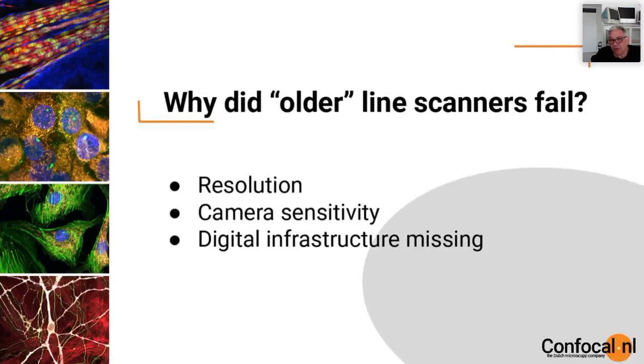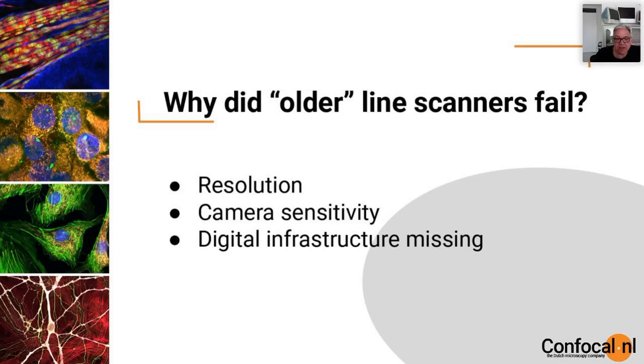Although the system design was good, commercially it failed. All the slit scanners I showed you failed because the resolution was not good enough. The cameras being used at that time — there were no scientific CMOS cameras, no EMCCD cameras, just very simple CCD chips that lacked sensitivity. Also, you could record images perhaps on videotape but there was no digital infrastructure to bring them into a computer. Deconvolution was not available in real time — a single image deconvolution took overnight. Because of the poor infrastructure, cameras, and sensitivity, these systems failed.